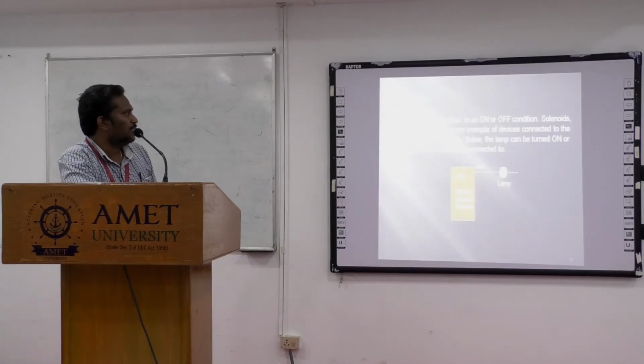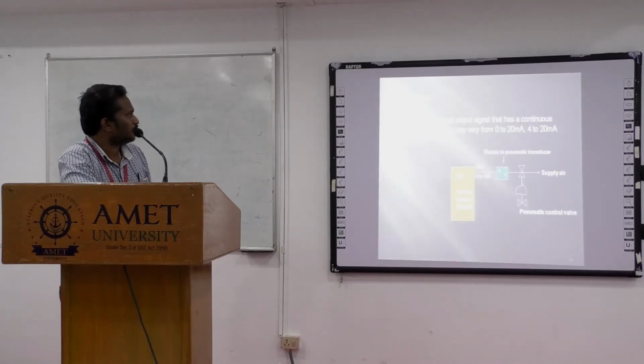Digital output. A discrete output is either in an on or off condition. Solenoids, contactor coils, and lamps are examples of devices connected to the discrete or digital outputs. Below, the lamp can be turned on or off by the PLC output it is connected to. Analog output. So this is an example of analog output. An analog output is an output signal that has a continuous signal. Typical outputs may vary from 0 to 20 milliampere, 4 to 20 milliampere, or 0 to 10 volt.